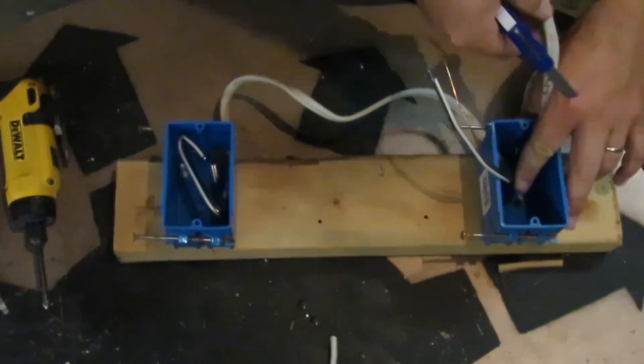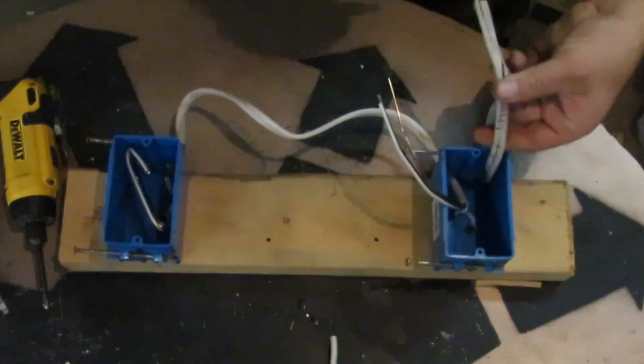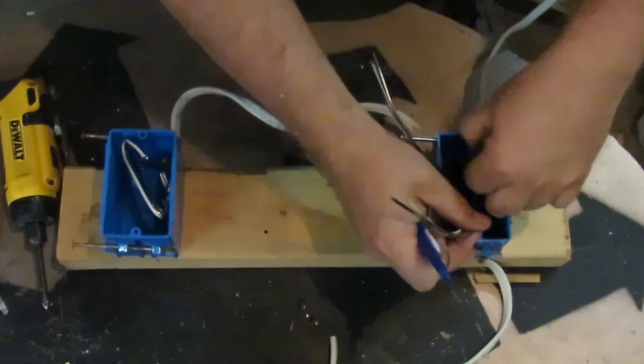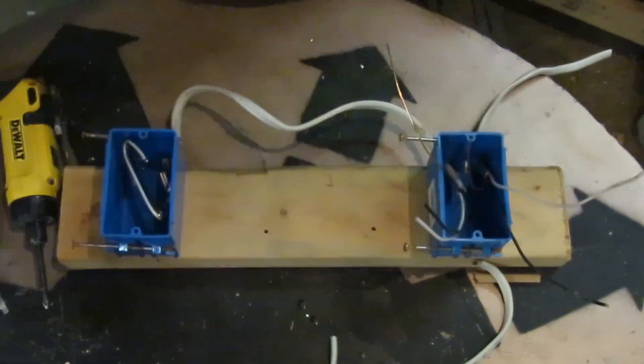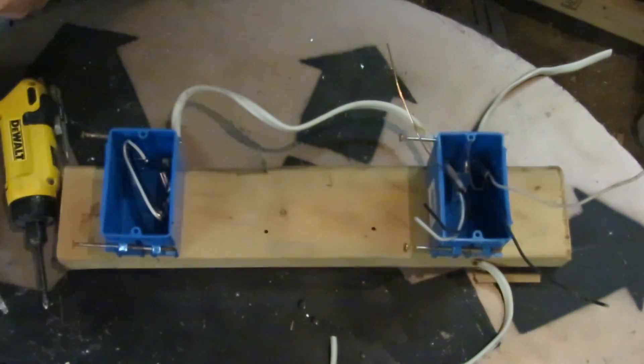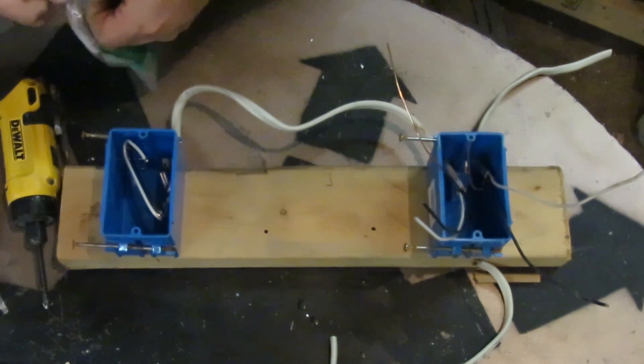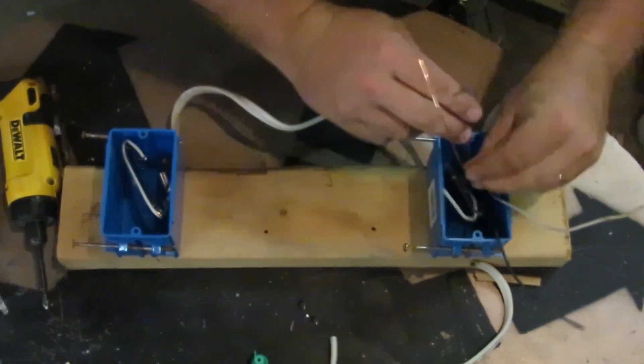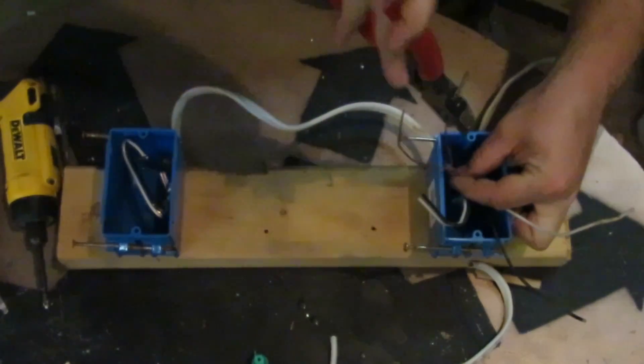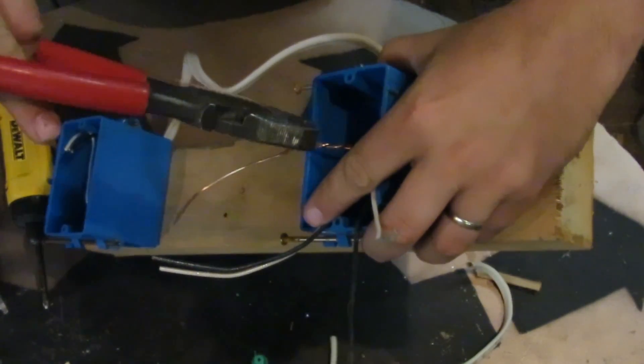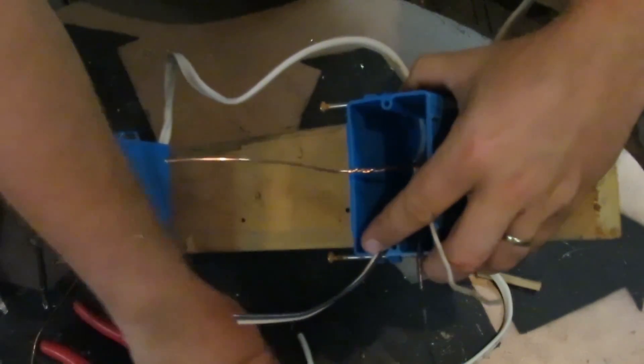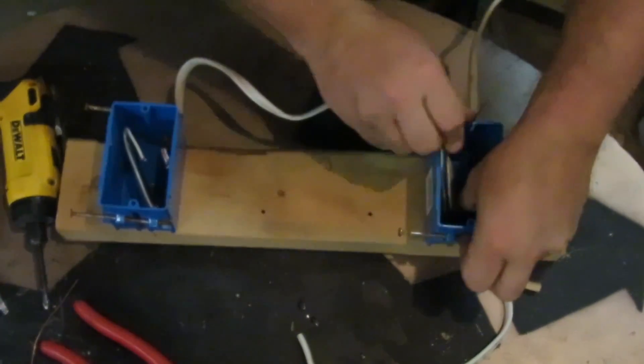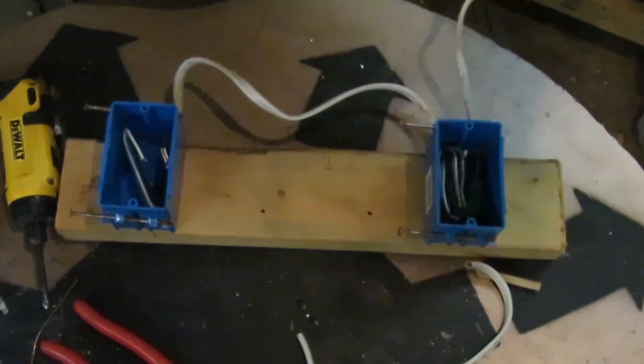And then you do the same with the two wires. You strip off the coating. The big difference with multiple wires in a box is that you have to make up your ground wires. And there's multiple different ways, but in this case I have these little green wire nuts. And they have a hole in the end of them where you can twist all your ground wires together and trim down all of them but one. And when you put the ground wire nut on there, you actually stick the one long piece of ground wire through and that will make up your ground wires. And you can get this pack at Home Depot for about $3 for 10. So it's not a bad price.